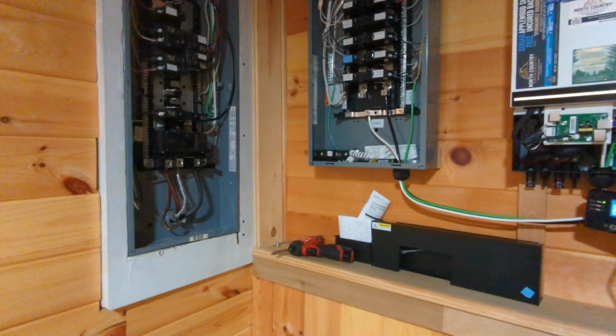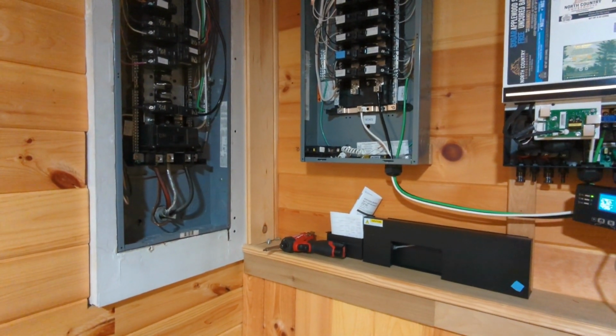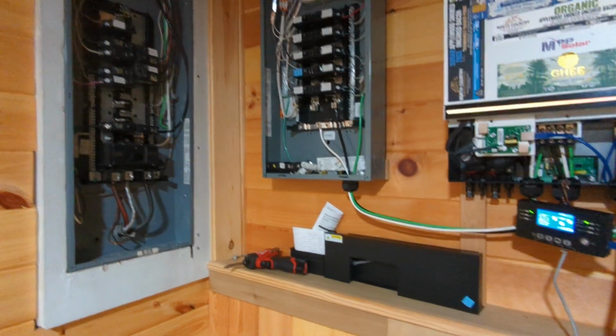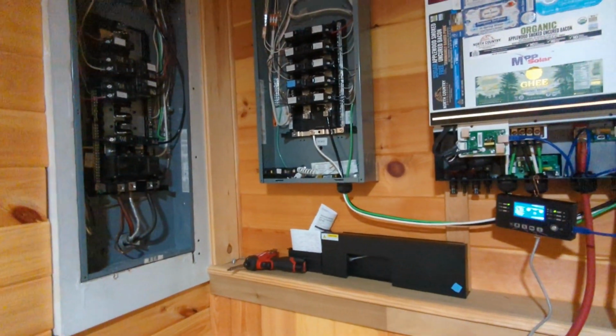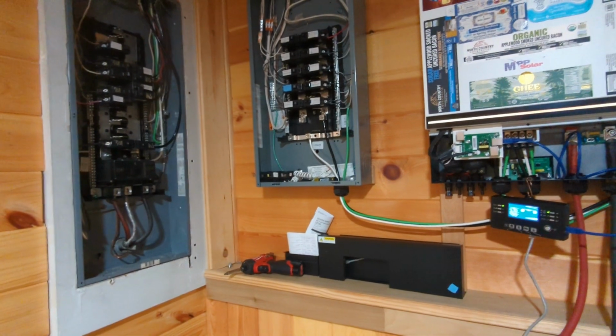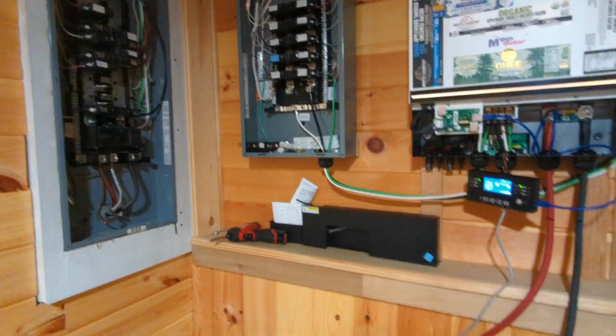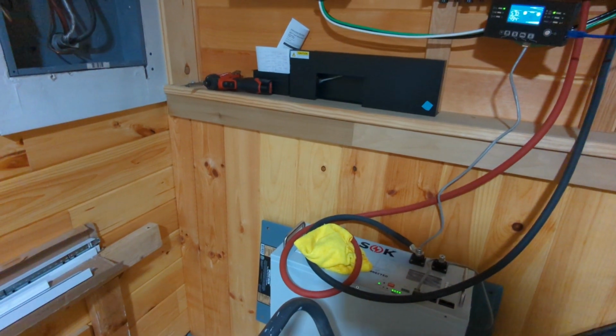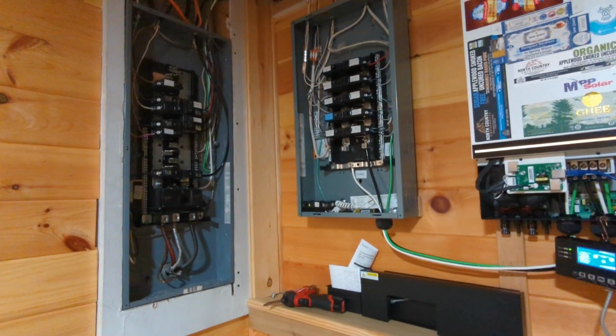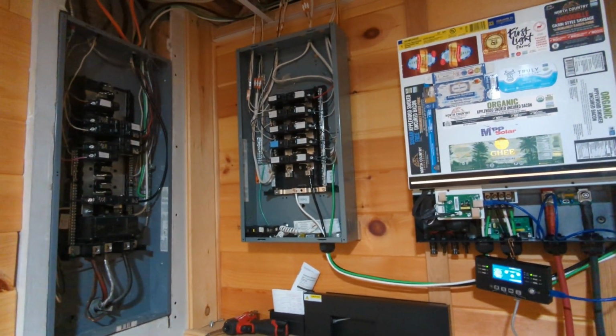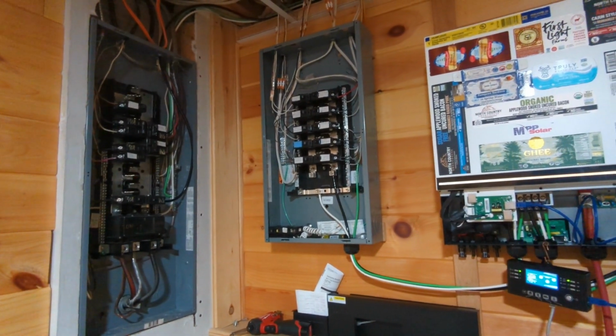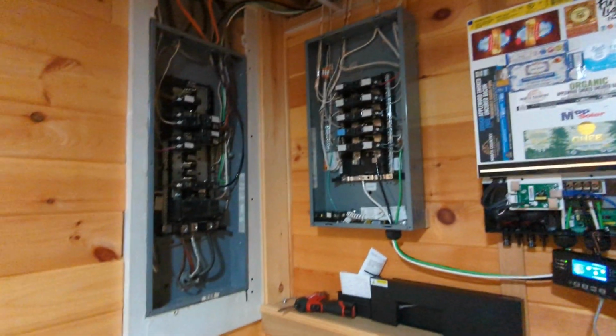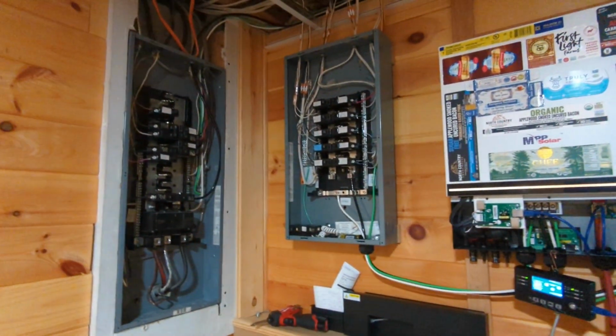So basically, if the AC input were to disconnect, whether it's from a power outage or if I manually switch off the breaker to the inverter, it will automatically pick up and switch over to using the battery as backup power. I do run the inverter in the UPS mode. I believe that is program option number 3 in the settings. There are 2 options, appliance and UPS, so there are no problems with switching over for things that have a computer chip or a CPU in them, like a desktop computer, a TV, a monitor, the Wi-Fi router. All those things switch over just fine.